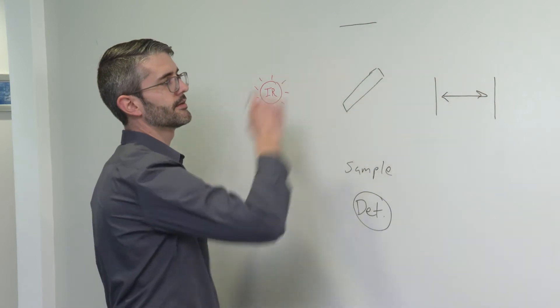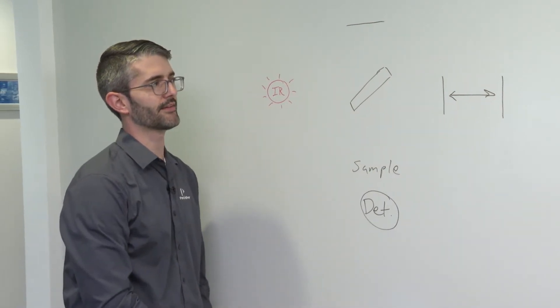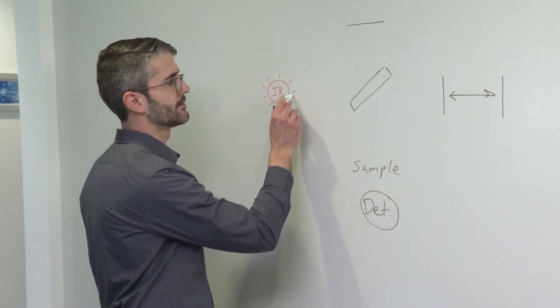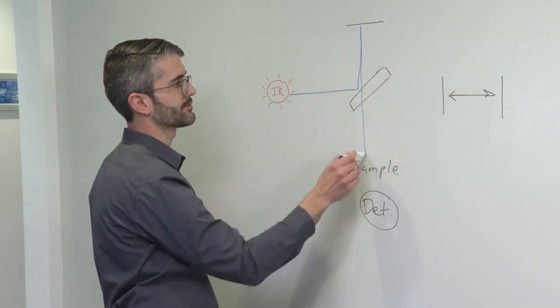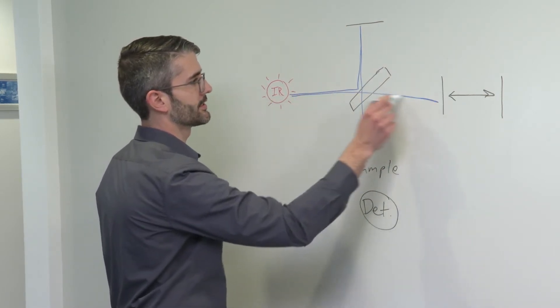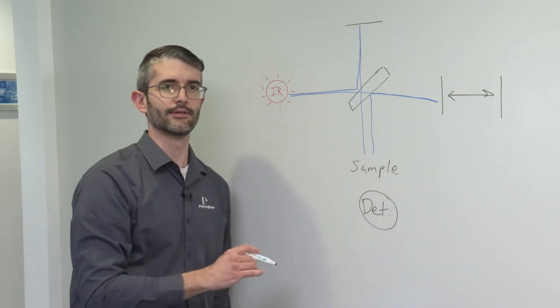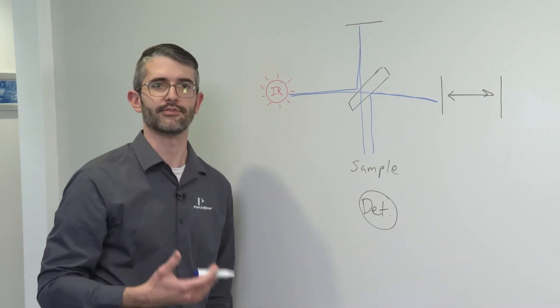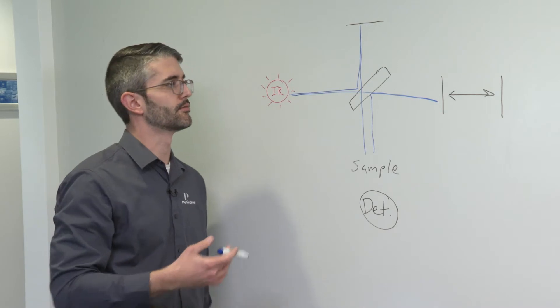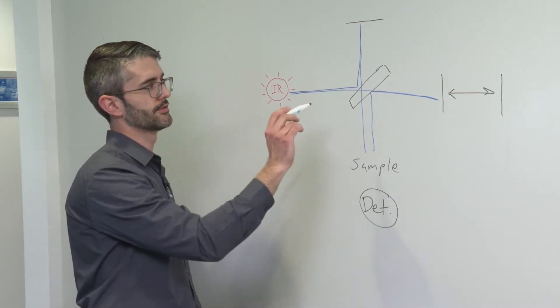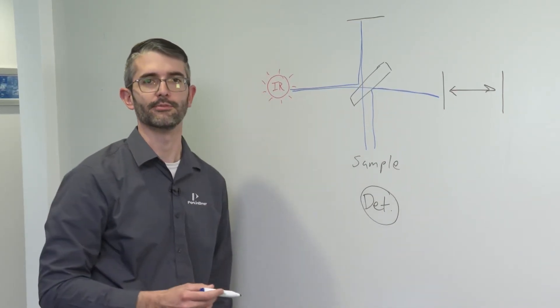This assembly here changes the optical path difference of the infrared light. So infrared light can take this path, infrared light can take this path. It's the interference of this light which produces what is known as the interferogram, which is the raw signal measured as part of the infrared measurement of a sample.